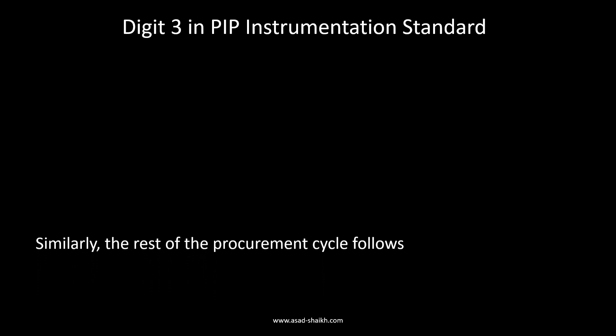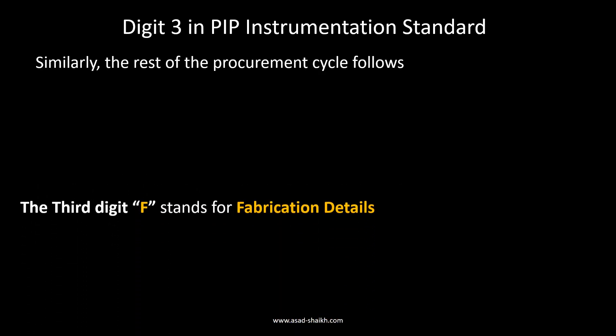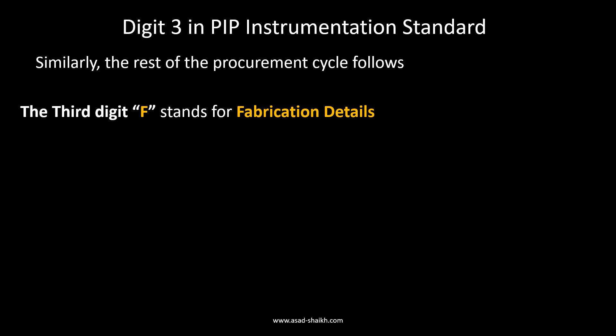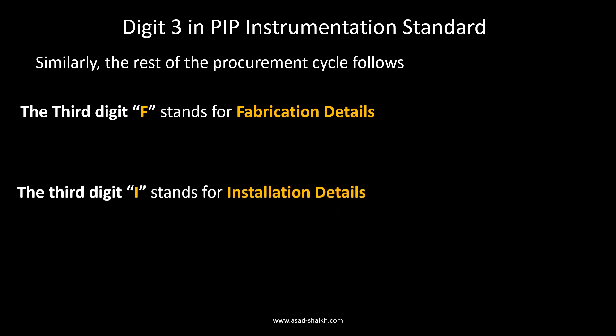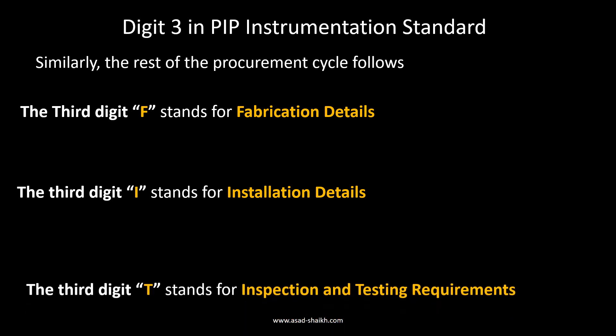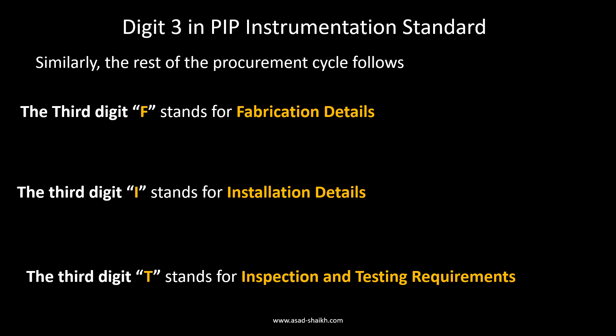After a particular instrument is specified, we need fabrication details — the third digit F covers this. After fabrication comes installation details: for example, how to install a DP flow meter transmitter relative to the tapping based on service. The third digit I covers installation. Similarly, the third digit T stands for inspection and testing requirements. The standards are thus linked to the procurement cycle: fabricate, install, then inspect and test.